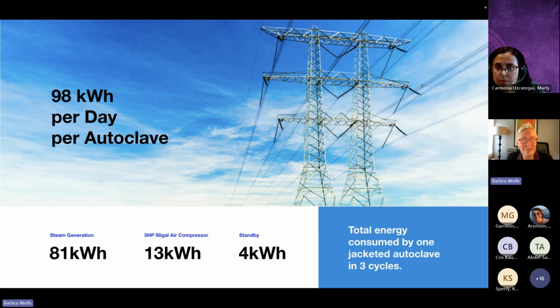Three operational hours of steam generation adds up to 81 kilowatt hours per day. The air compressor running for about 3.5 hours gives us the 13 kilowatt hour figure, and an autoclave with an integral steam generator typically uses about 200 watts on standby. So if we multiply that 0.2 kilowatts by 21 hours, that adds 4.2 kilowatt hours per day.